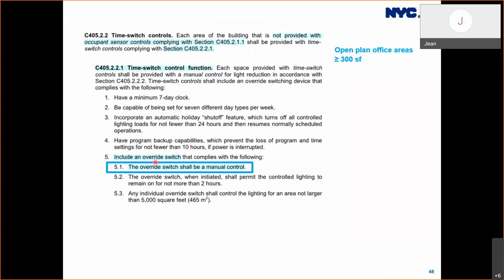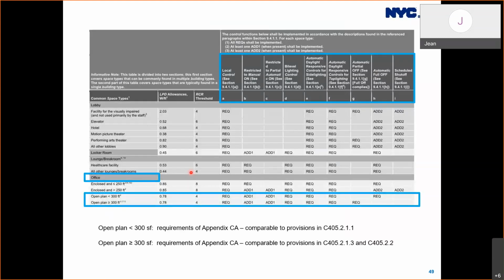And one of the functions includes an override switch, and that should come with a manual control. So the bottom line, the open plan office areas, whether smaller or larger, they both require manual control. And we could compare this with the ASHRAE section. Like I said, ASHRAE has this controls requirement nicely formatted in a table.